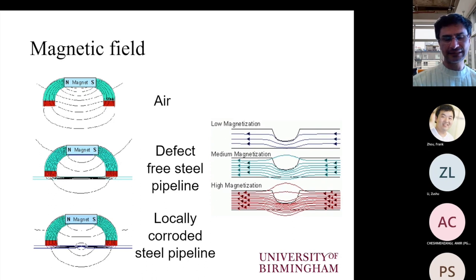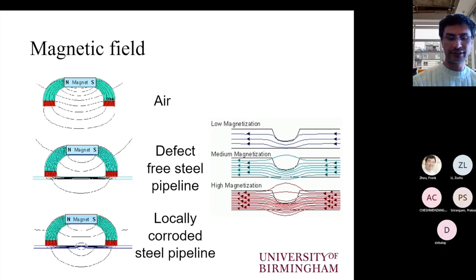So the principle of magnetic flux leakage is based on magnetizing the sample, as I said earlier. And of course, in order to magnetize it, it has to be ferromagnetic. You can see on the left-hand side a series of schematic diagrams. You can see how the flux distributes itself when we have no ferromagnetic component in the vicinity where the flux field is present. And then when we have a pipeline which is defect-free, the sample will be magnetized, but no flux leakage, or no sufficient flux leakage, will occur to give us a measurable signal. In the case where we have corrosion or a crack defect which causes enough leakage to occur, then some of the flux will leak. And of course, that is what we are going to try to detect with our Hall probes or with our coils.